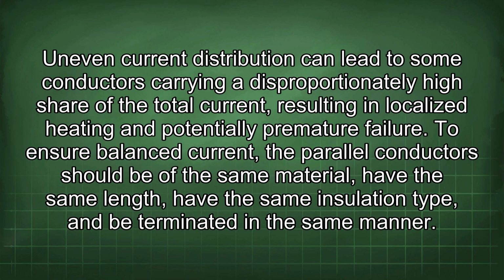Secondly, it is crucial to calculate the current in each parallel conductor to ensure that the current is balanced. Uneven current distribution can lead to some conductors carrying a disproportionately high share of the total current, resulting in localized heating and potentially premature failure. To ensure balanced current, the parallel conductors should be of the same material, have the same length, have the same insulation type, and be terminated in the same manner.